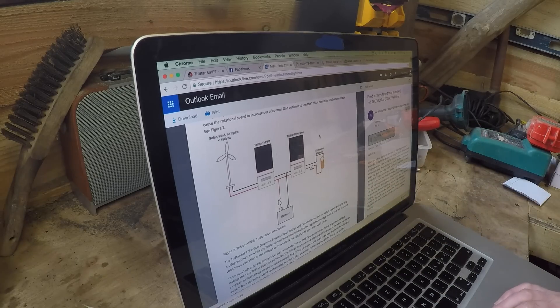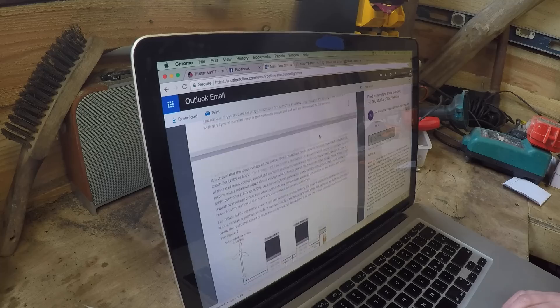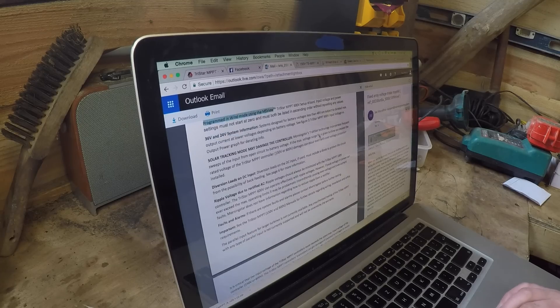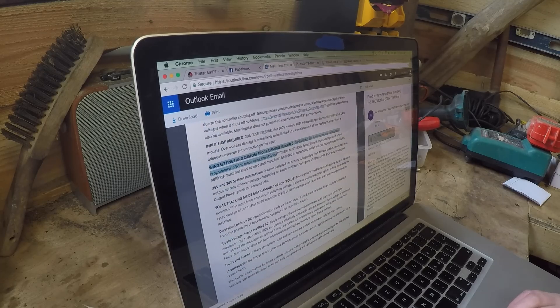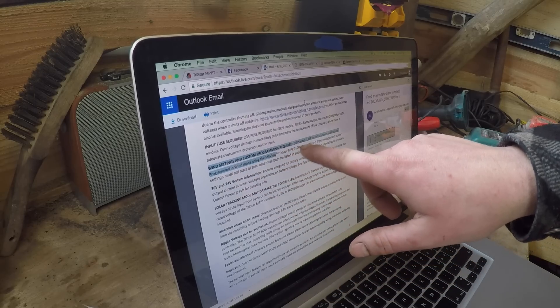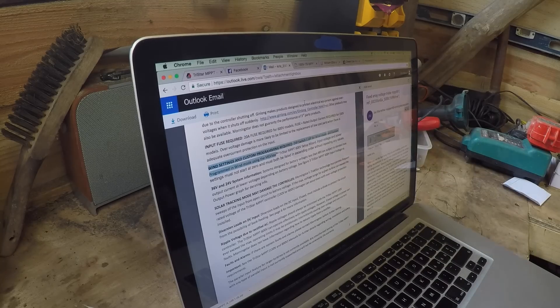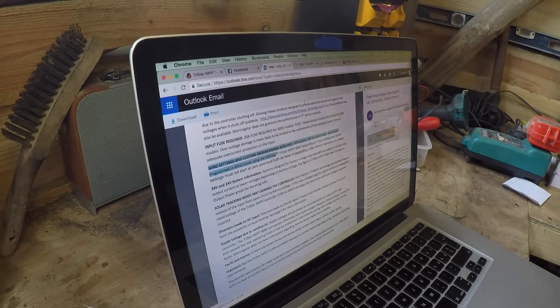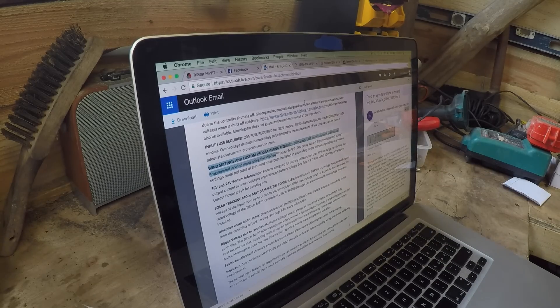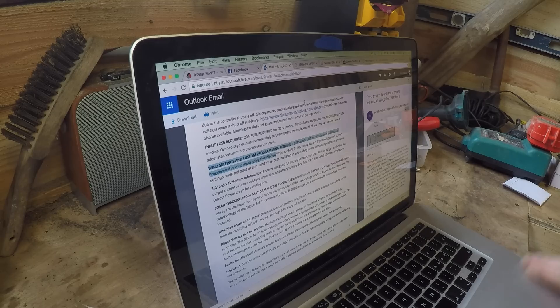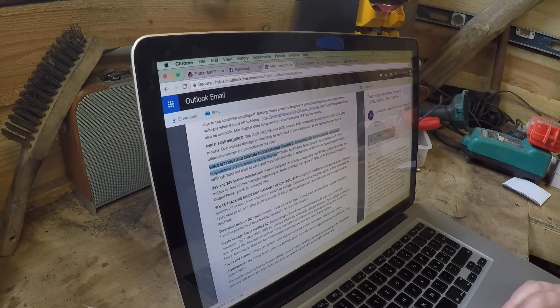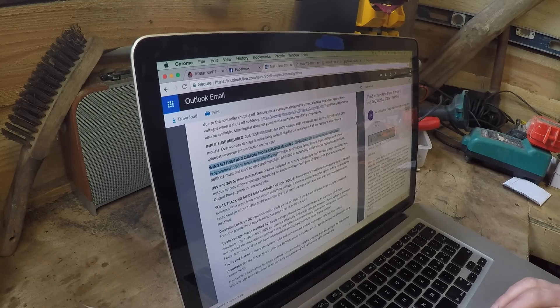I thought I'll read through it anyway and I just so happened to notice that it says here wind settings and custom programs required dip switch one in the up position. And my dip switch was in the down position and I thought maybe something to do with that dip switch being in the up position that allows you to program custom settings. So I tried that and I had a little bit of success and things started working properly.